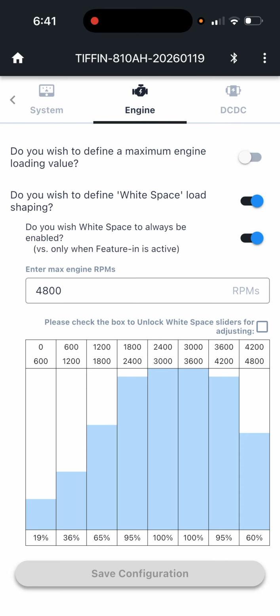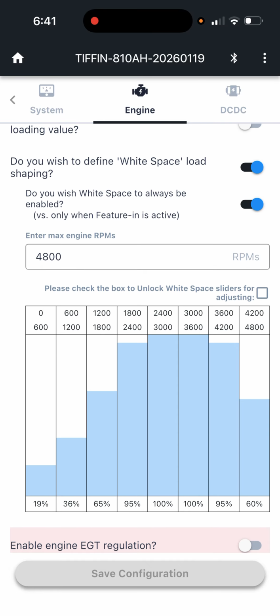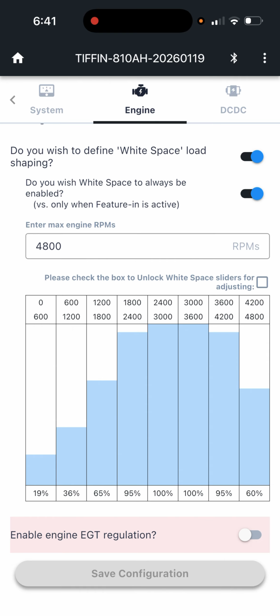Engine - this is where I changed the white space shaping. Best practices are to make sure the curve is smooth, with no quick jolts between the different ranges of RPM. In my previous setting, this was really being ignored anyway, because half power mode was kicking in and the alternator poles setting was not correct, so it wasn't even reading or able to do the shaping. Now it's doing the shaping just beautifully, and I'll show you that in a minute.